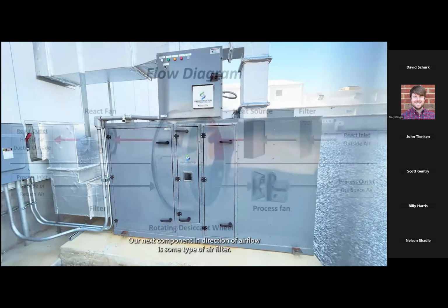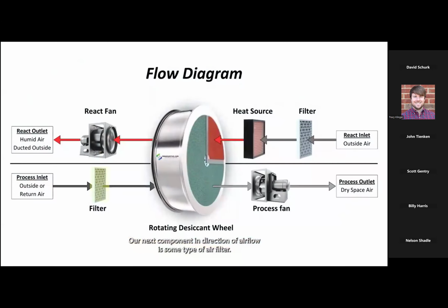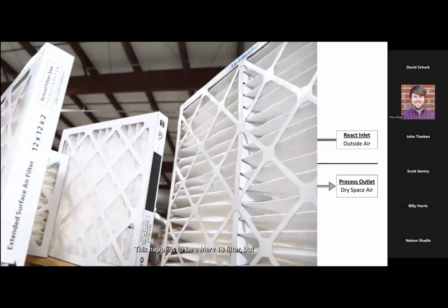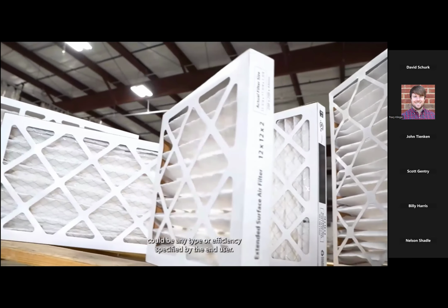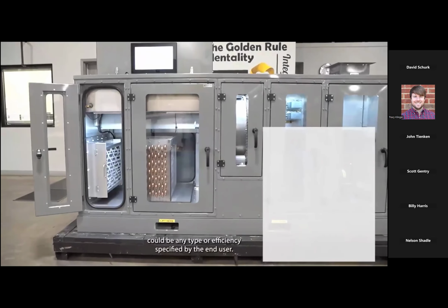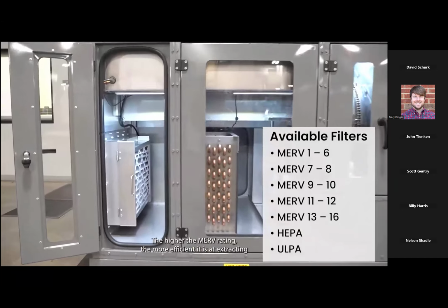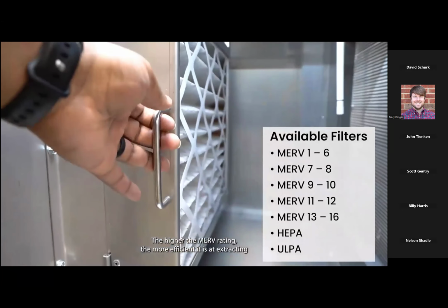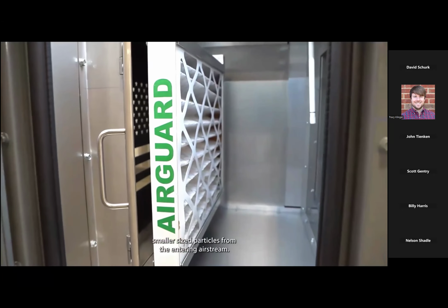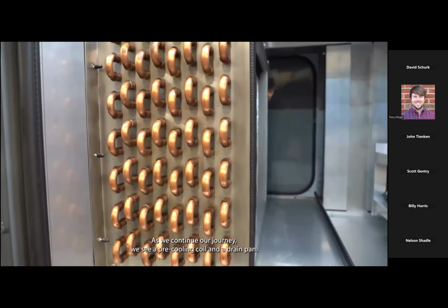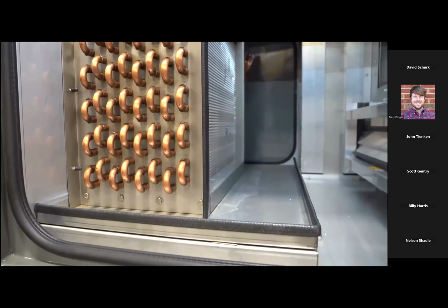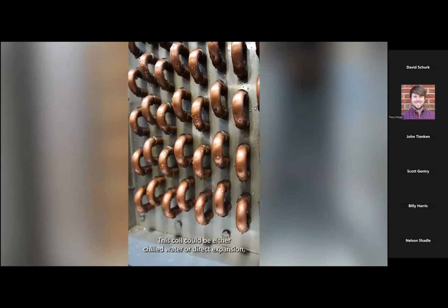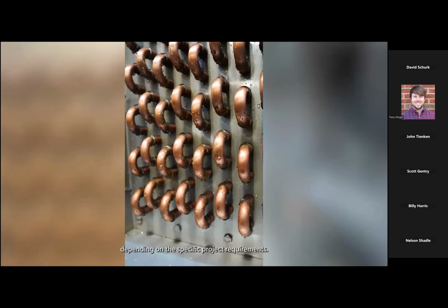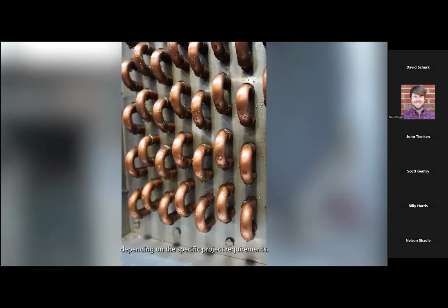Our next component in direction of airflow is some type of air filter. This happens to be a MERV 13 filter, but could be any type or efficiency specified by the end user. The higher the MERV rating, the more efficient it is at extracting smaller sized particles from the entering airstream. As we continue our journey, we see a pre-cooling coil and a drain pan. This coil could be either chilled water or direct expansion, depending on the specific project requirements.